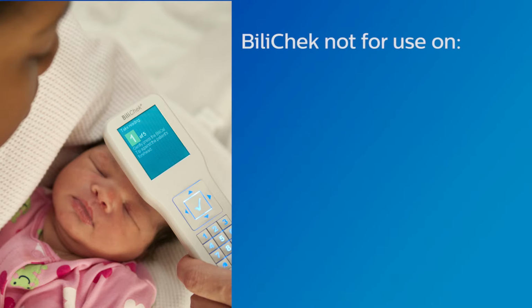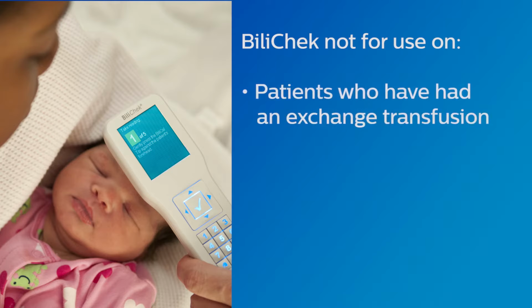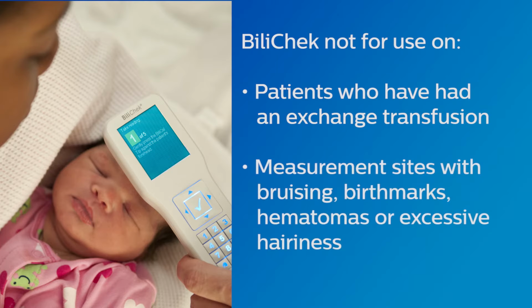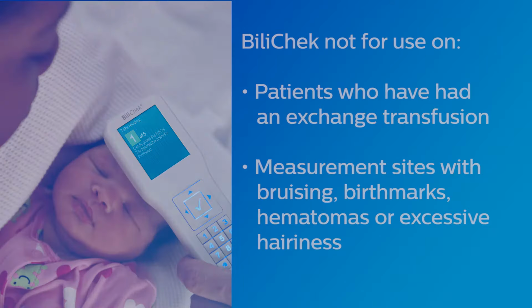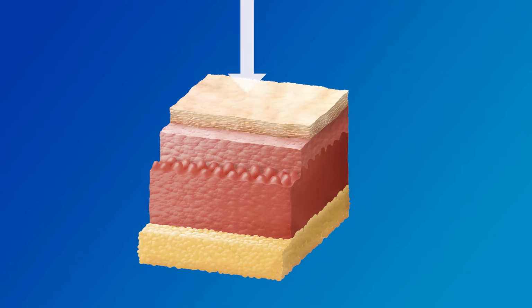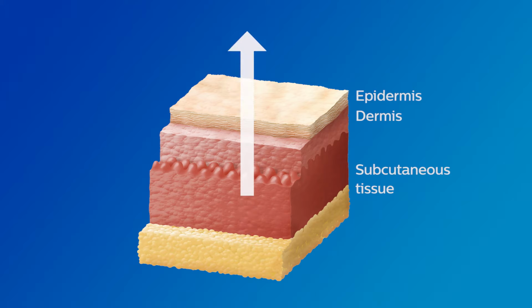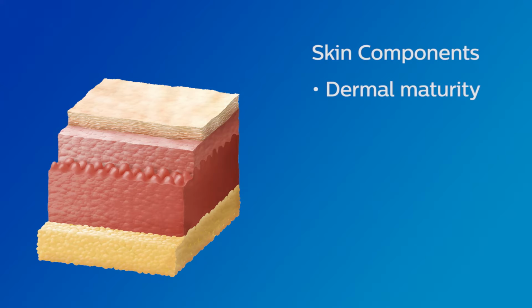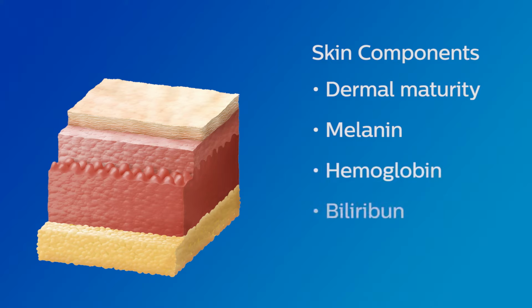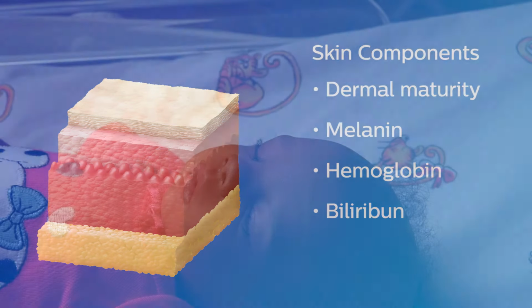The BiliChek should not be used in patients who have undergone an exchange transfusion or on measurement sites that have bruising, birthmarks, hematomas, or excessive hairiness. The BiliChek works by directing white light into the skin of the newborn and measuring the intensity of the specific wavelengths that are reflected back from the major skin components: dermal maturity, melanin, hemoglobin, and bilirubin. The intensity of the reflected light is converted to absorbance units, called optical density, for analysis.